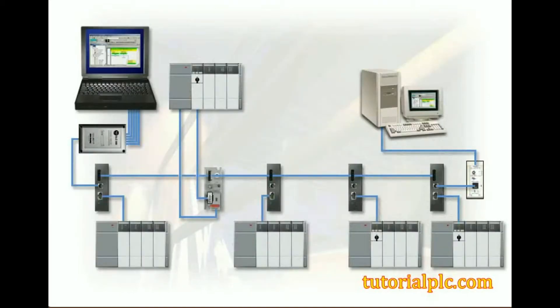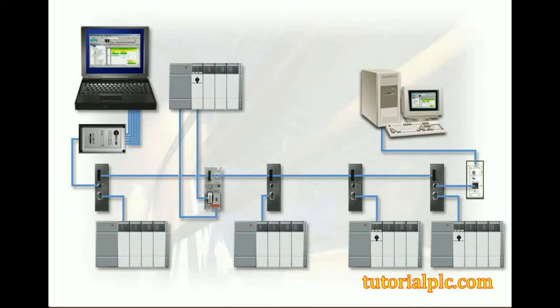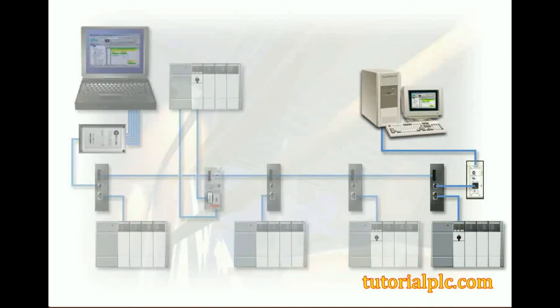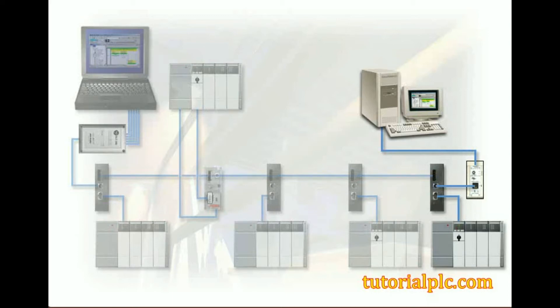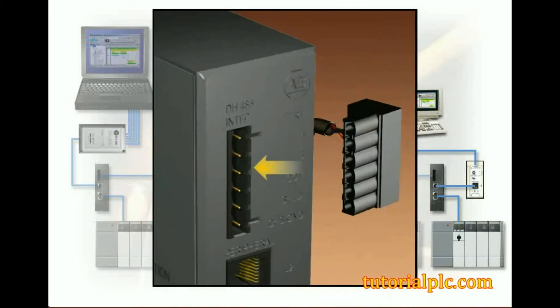If we wanted a computer and an SLC 503 processor to each be independently connected to a DH-485 network, we would need to add a 1747 AIC link coupler module. This type of configuration requires that an AIC module be installed between a UIC module and an SLC 503 processor. In this way, an SLC processor and a computer are each separately connected to the DH-485 network and can communicate with other devices in addition to each other. An AIC link coupler module is externally powered and allows direct connectivity to a DH-485 network via a 6-pin Phoenix connector.